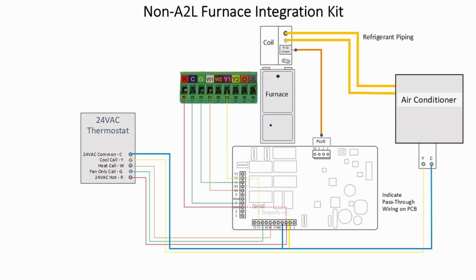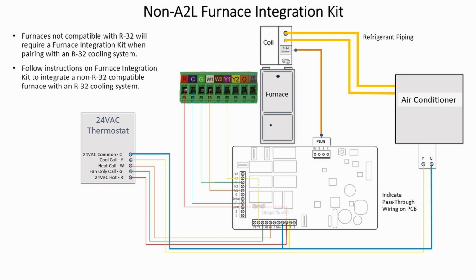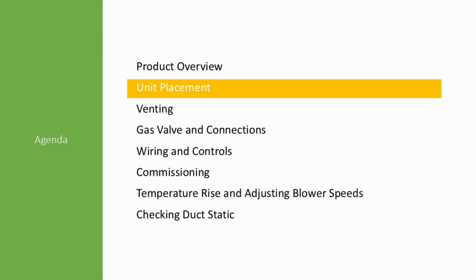Non-A2L furnace integration kit. Furnaces not compatible with R32 will require a furnace integration kit when pairing with an R32 cooling system. Follow instructions on the furnace integration kit to integrate a non-R32 compatible furnace with an R32 cooling system. Unit placement.